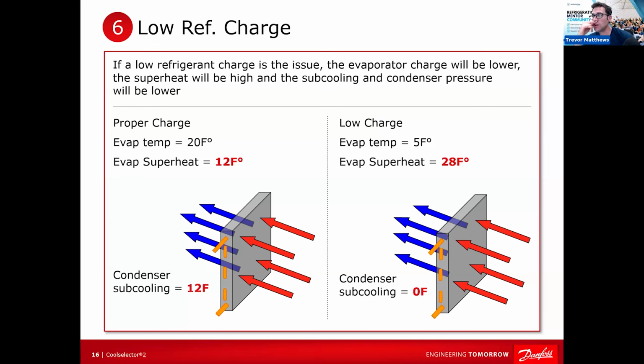Let's talk a little bit about low charge. What happens? All right. So low charge is one of those things where you want to identify, is it low charge or is it low flow rate? So let me clarify this. So a proper charge, everything else is working properly. This is a walk-in cooler, right? It's got 20 degrees evaporator temp, could be 22, could be 24, whatever, medium temp. You got 12 degrees of superheat. She's chugging along. It's got some load on it.